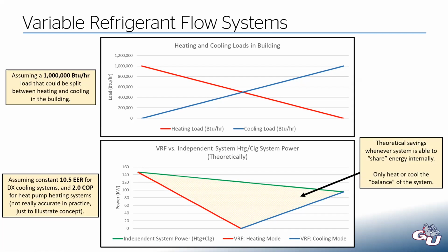So if you install a VRF system that is constantly on this side, it's in cooling all day, every single unit, or on the opposite side, you're not going to see great energy savings. But if you have a lot of time somewhere in here, you can see there's substantial savings that could be gained. And again, this is a bit of an oversimplification, assuming a constant 10.5 EER and a 2.0 COP. In reality, the efficiency would vary depending on how hot or cold it is outside. But I hope this helps show what's going on and why there can be such substantial savings with the VRF system.